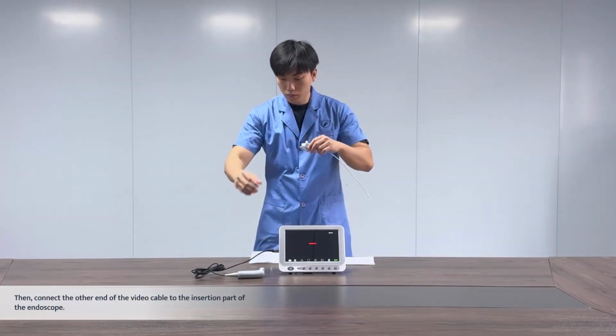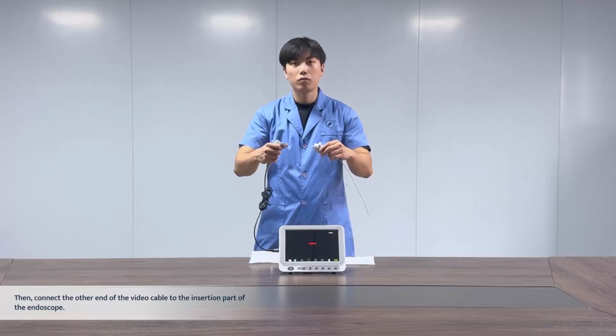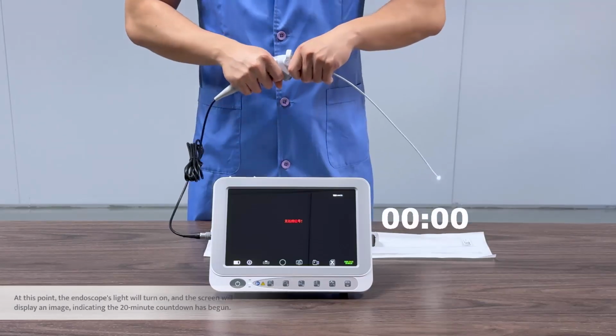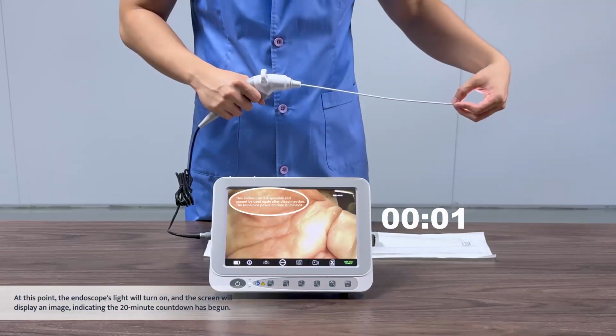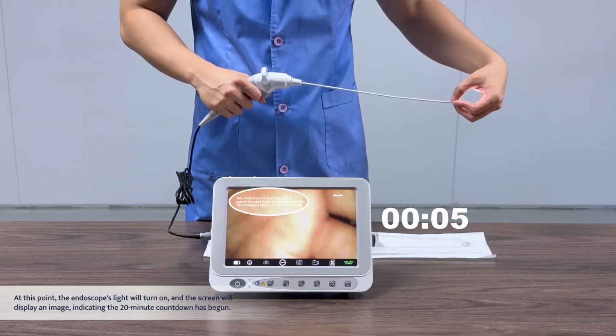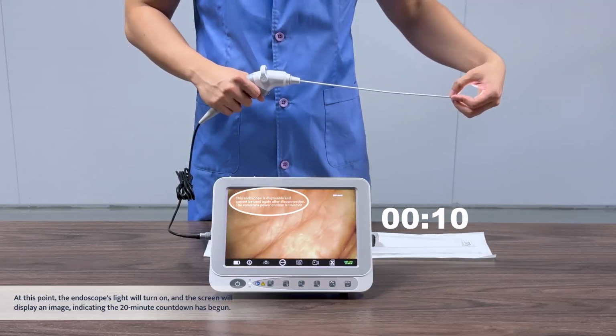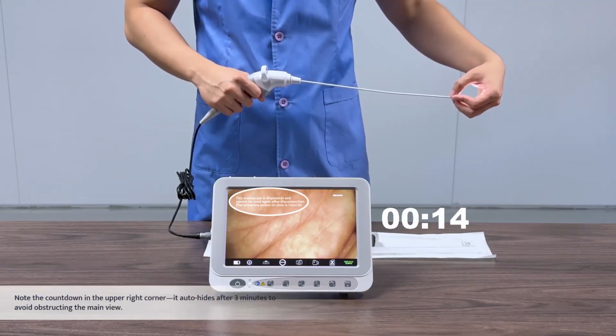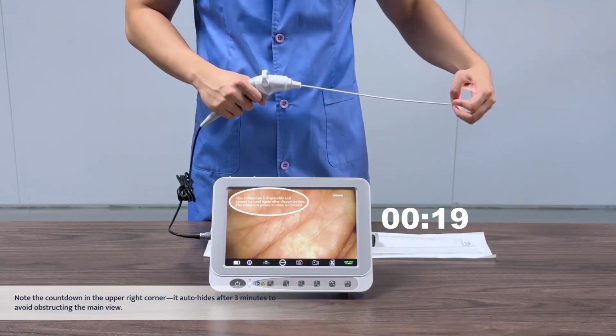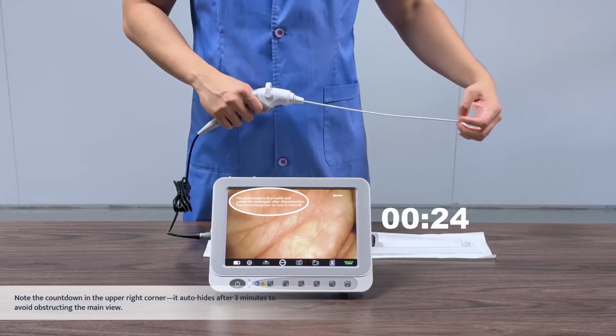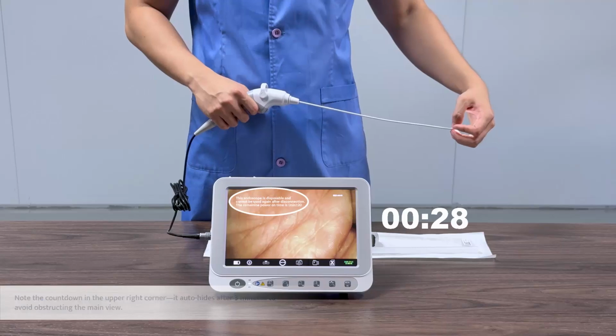Then, connect the other end of the video cable to the insertion part of the endoscope. At this point, the endoscope's light will turn on and the screen will display an image indicating the 20-minute countdown has begun. Note the countdown in the upper right corner. It auto-hides after 3 minutes to avoid obstructing the main view.